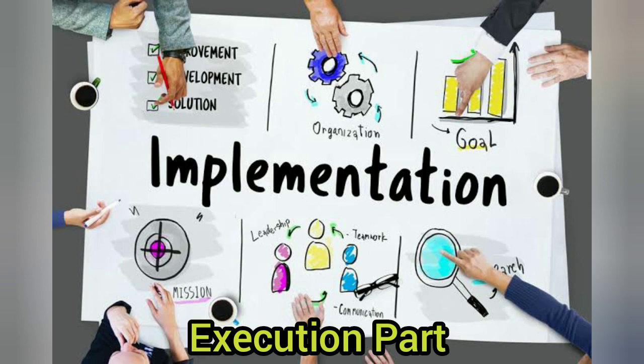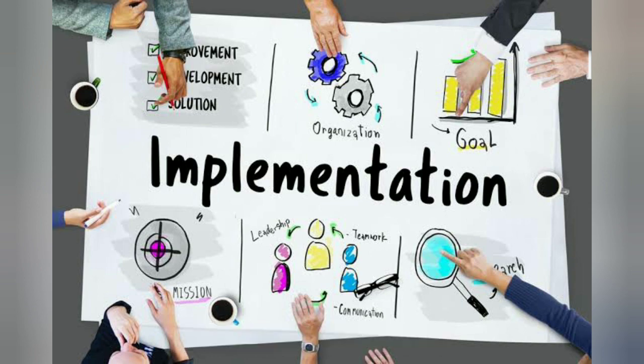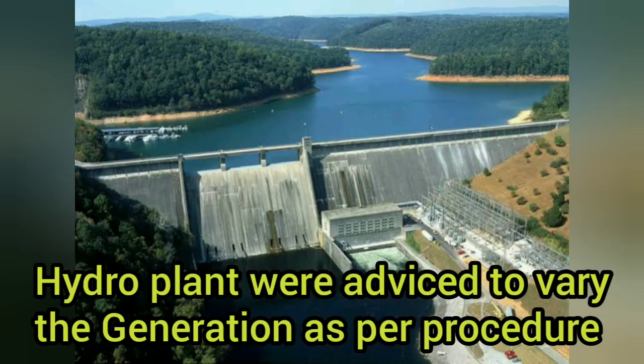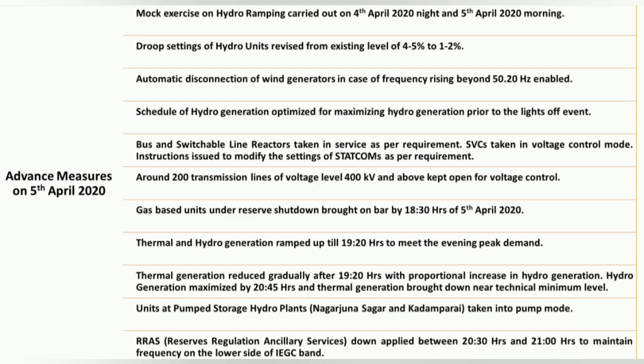So it's now time to implement all these things. Firstly, various steps were taken. Hydro stations were advised by respective RLDCs to vary generation as per the detailed procedures. Confirmation about change of governor droop settings at hydro units was taken. Wind generators were to enable the over frequency setting, that is, automatic disconnection of the incoming feeders from wind generators in case of frequency rising beyond 50.20 Hz.